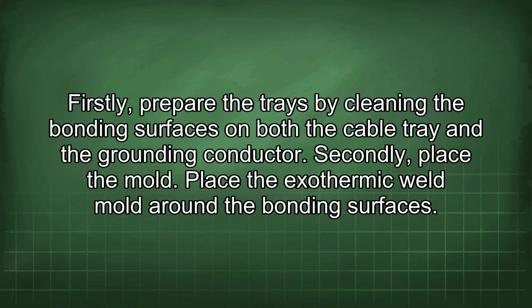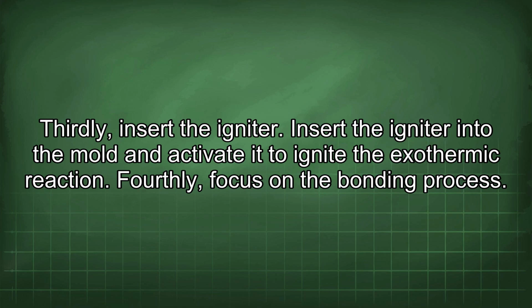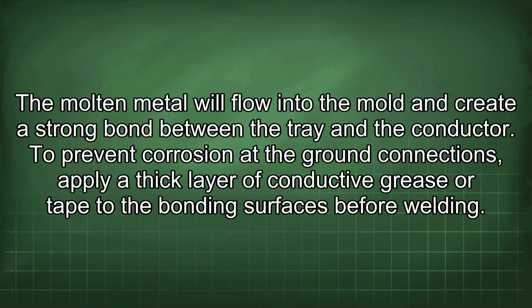Firstly, prepare the trays by cleaning the bonding surfaces on both the cable tray and the grounding conductor. Secondly, place the mold. Place the exothermic weld mold around the bonding surfaces. Thirdly, insert the igniter. Insert the igniter into the mold and activate it to ignite the exothermic reaction. Fourthly, focus on the bonding process. The molten metal will flow into the mold and create a strong bond between the tray and the conductor.